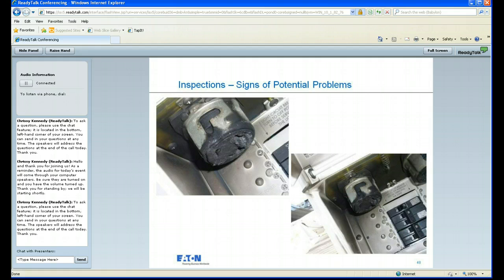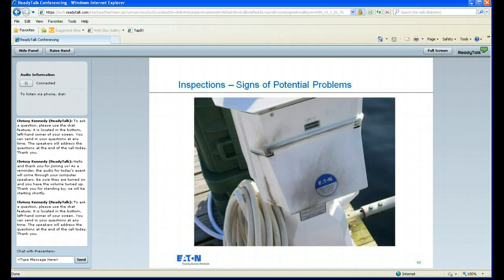Some things you're looking for, and this is not something that needs to be done by a certified electrician on a monthly basis. This is something you can take a look for when you're going out, talking to your boaters, talking to people within the marina. If you see any signs of melting or burning, that's a sign of a potential problem. Could be related to the grounding system, could not be, but more importantly, it's a sign of a potential fire. So that's something you can look for on your daily inspections or daily walkthroughs that you or your dock hands may be doing.